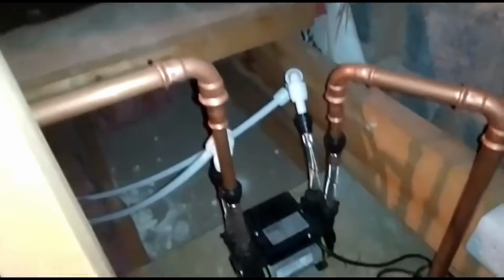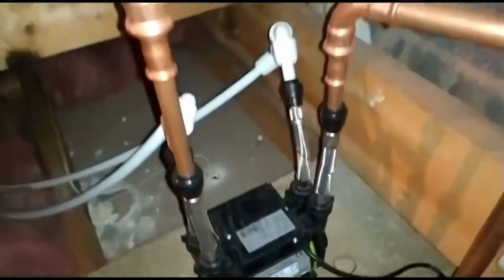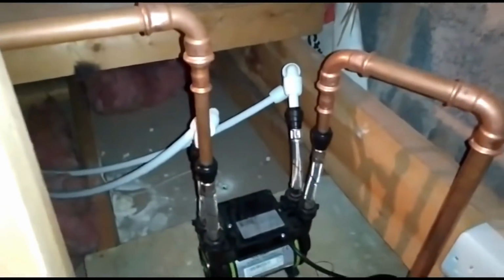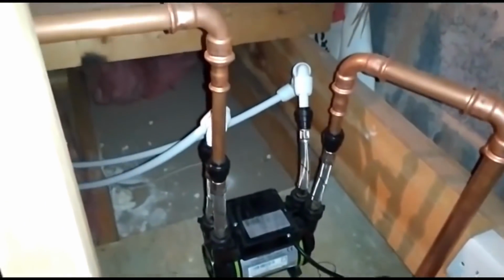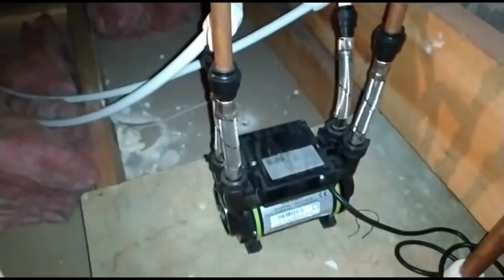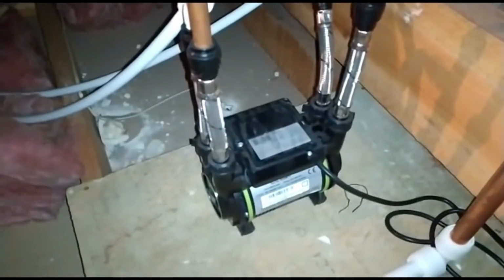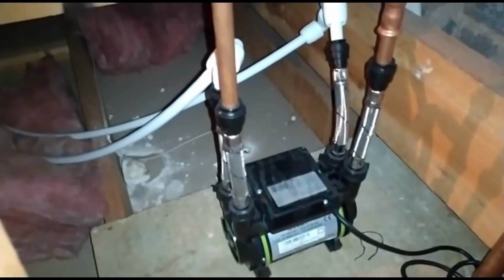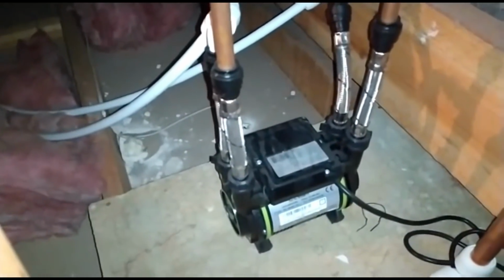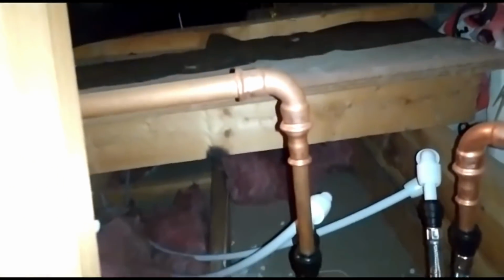Also on this one, this pump's in the loft. It's a Salamander pump, love them or hate them, in the loft space, and the tank's just there. This is not a negative head pump or universal pump, so it's been fitted in the wrong dimensions. It should be a negative head pump if the pump is only that sort of distance from the tank, and this feed here is actually higher than the tank level, the bottom of the tank level.